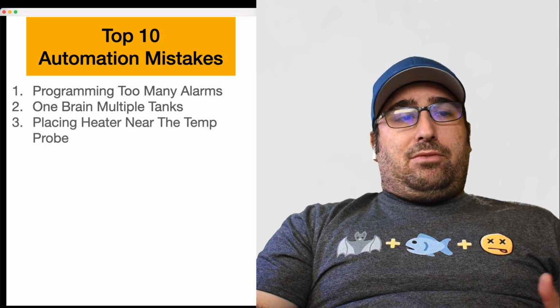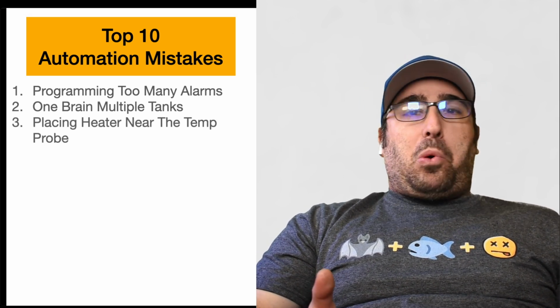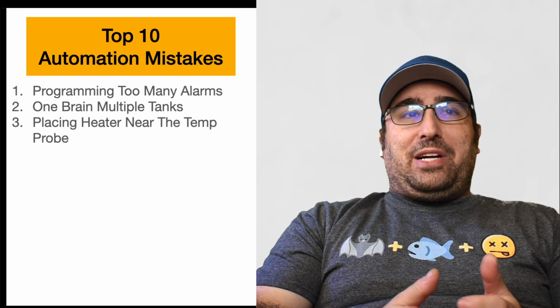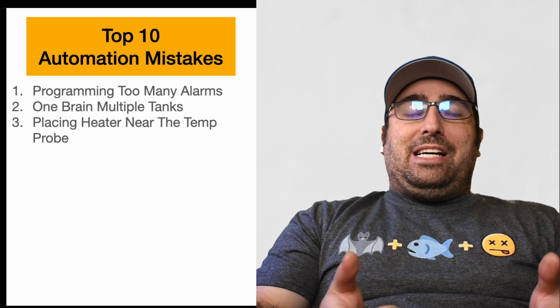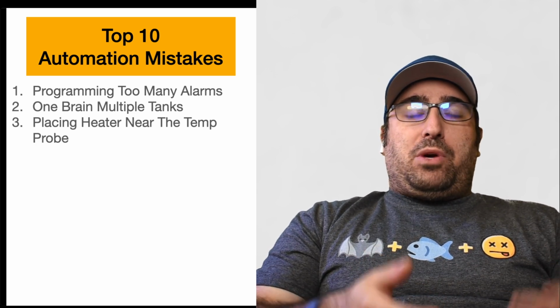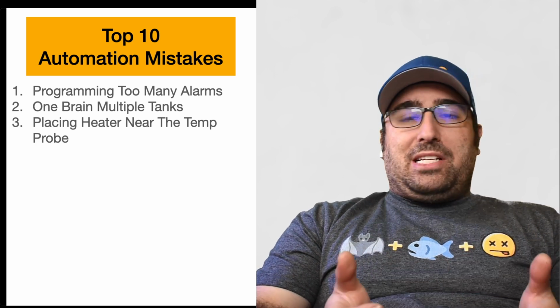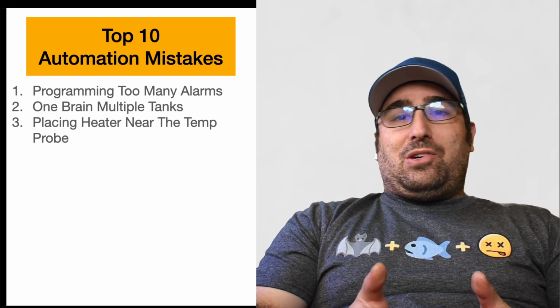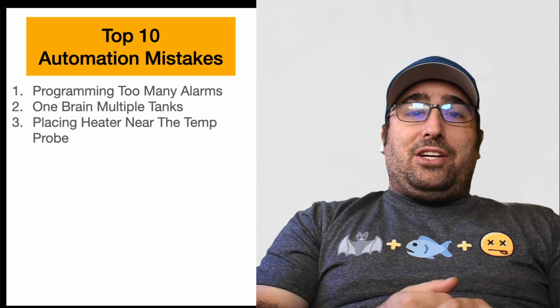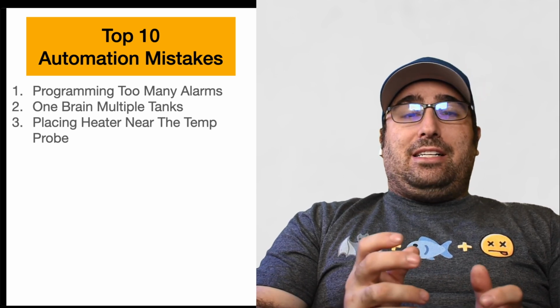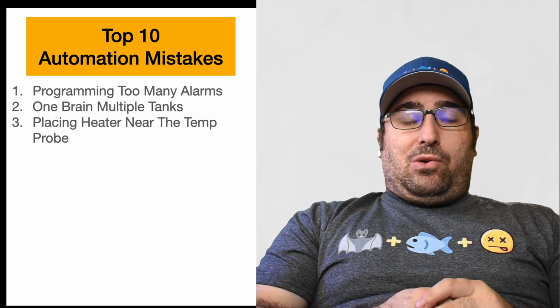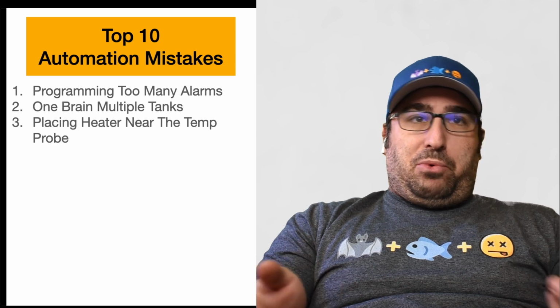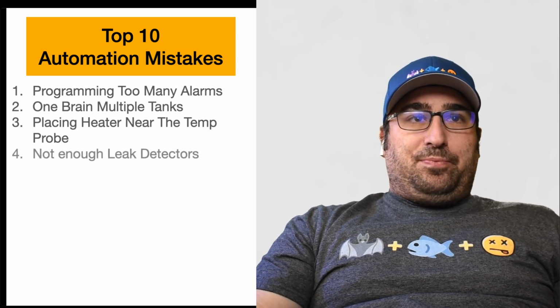Number three is a very important thing that I notice a lot of people doing, and that's placing the heater inside the return tank where your temp probe is. I've noticed that if you put the heater anywhere near the temp probe, you'll get very erratic temperatures. So my recommendation has always been, don't put your heater near your temp probe.